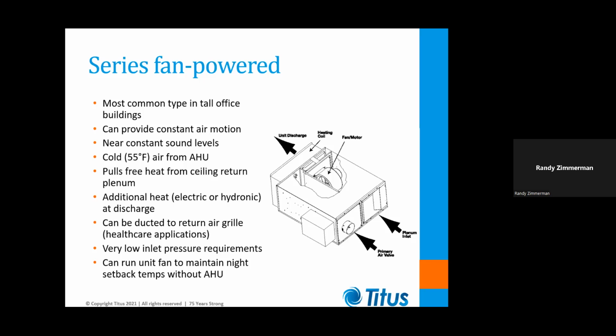Now, on a series fan-powered box, the fan runs all day long and then simply turns off at night and on weekends. But the fan is also free to come back on during nights and weekends. And that's one of the things people really like about fan-powered terminal units. You can maintain night setback conditions on nights and weekends without running the air handler, because the fan box has its own source of airflow.